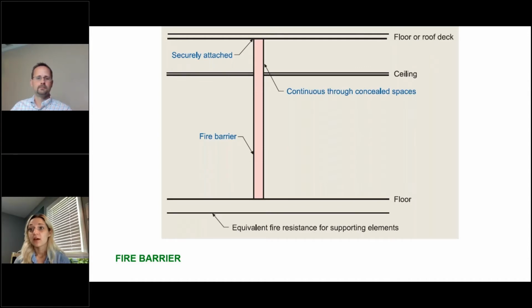So this is a great graphic. It shows basically that it goes from the floor up to the floor or roof deck above, and it pops up through the ceiling. So if you're in the field and you're trying to determine whether a wall is a fire barrier or something lesser, it's usually a pretty good idea, if you can, to pop up above the ceiling and see if it keeps going.